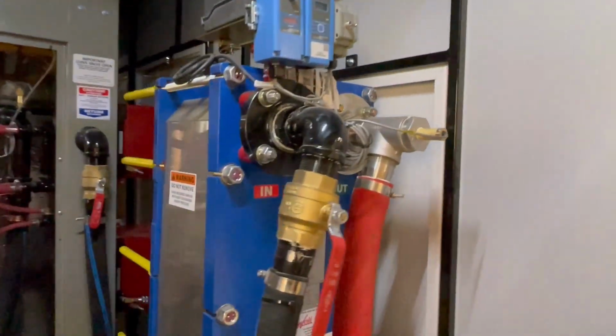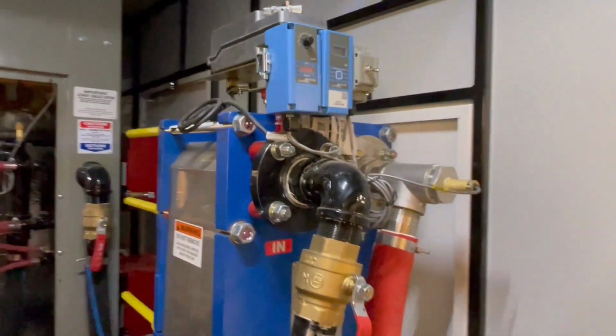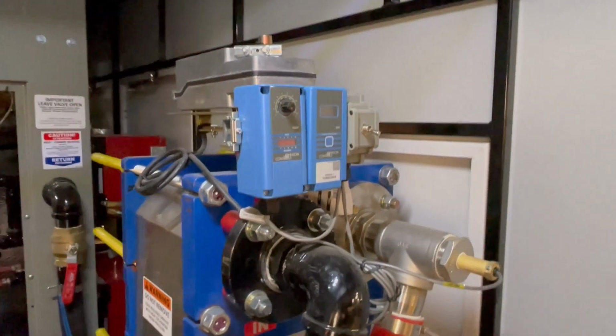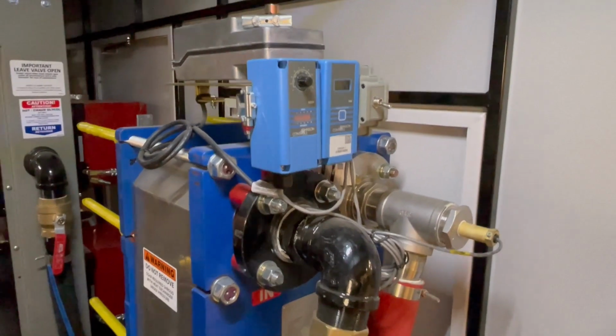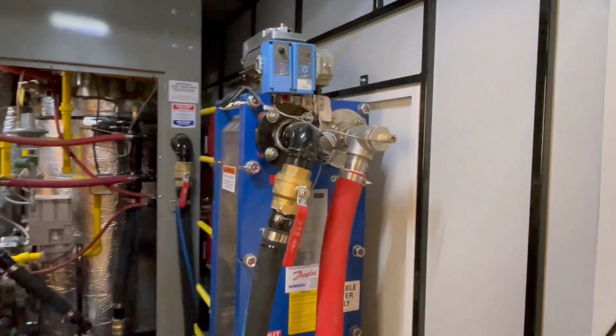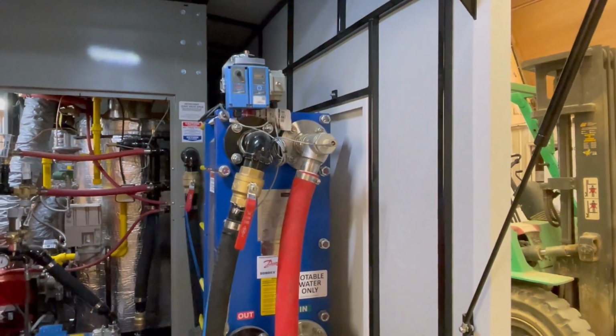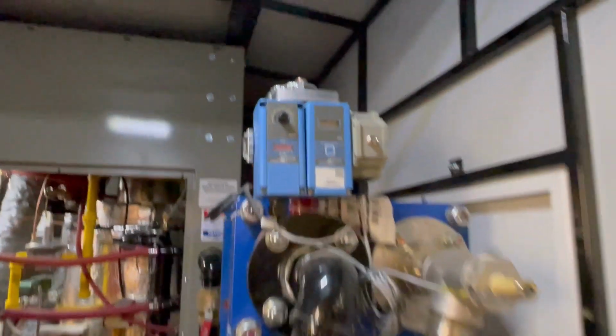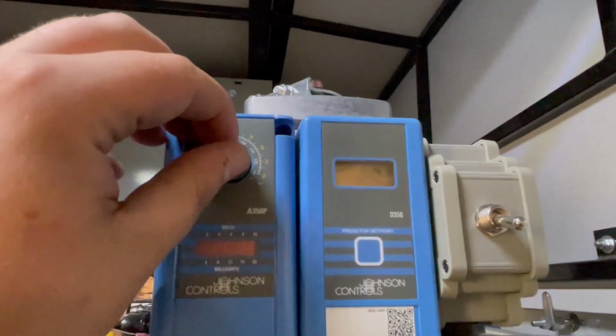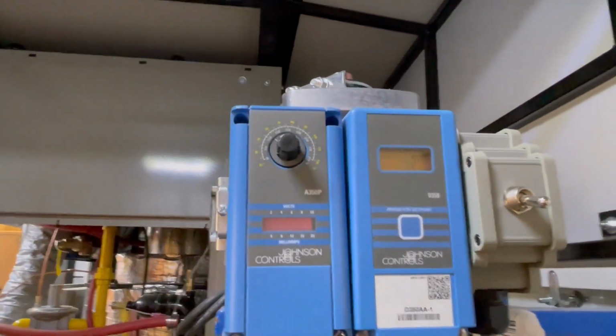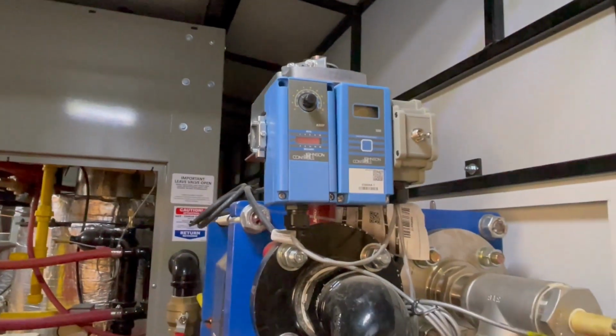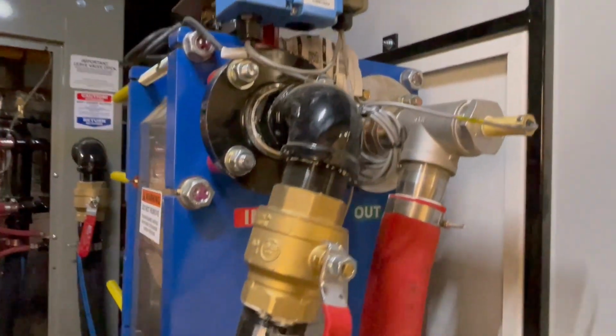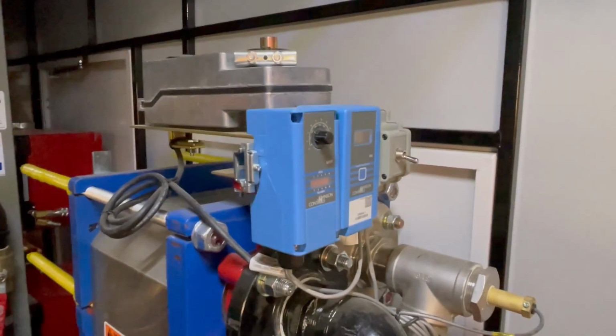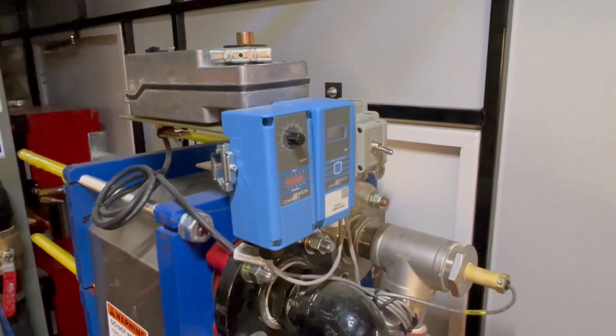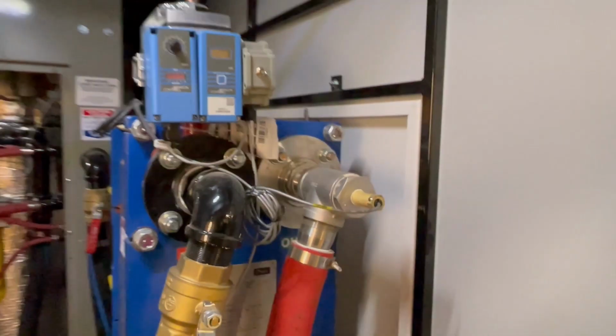An actuated valve is in line to the glycol inlet of the plate heat exchanger. This valve opens and closes based on the temperature of the water on the other side of the plate. You can adjust your water temperature set point with the temperature controller dial and check that temperature with the digital display beside it. As the water temperature rises to the set point, the actuated valve will slowly close or open the glycol inlet to maintain a water temperature of your choosing.